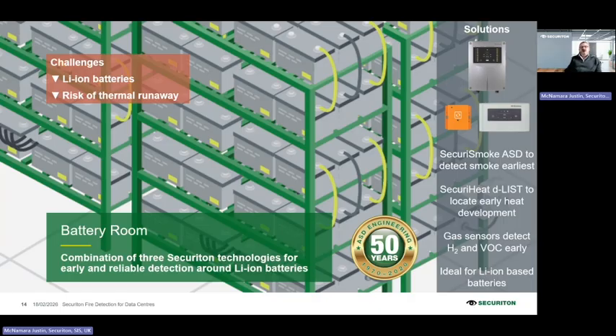However, we have a solution. Securiton has partnered with a company called InfraSensing that has developed a range of VOC sensors, as well as flammable gas detection, to detect any H2 given off when there is a battery failure. We strongly recommend the addition of at least aspirating smoke detection for a further enhanced level of smoke detection. The key thing in these lithium-ion battery areas is to ensure we have the right detection technology, and InfraSensing with its VOC and flammable sensors is definitely the right solution.